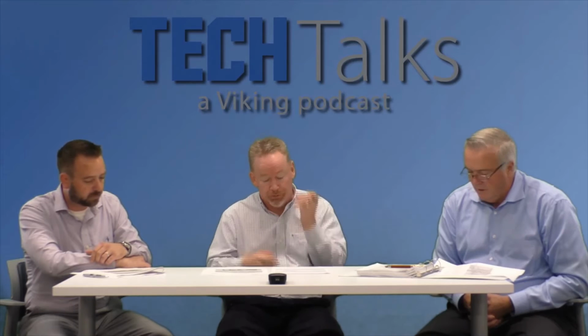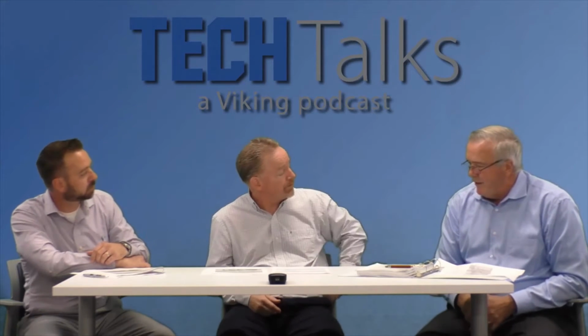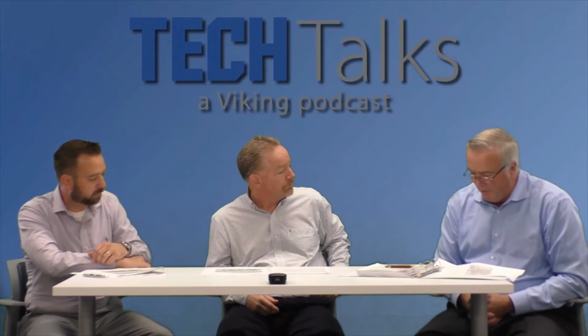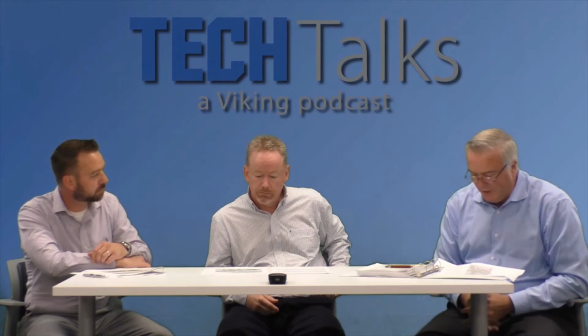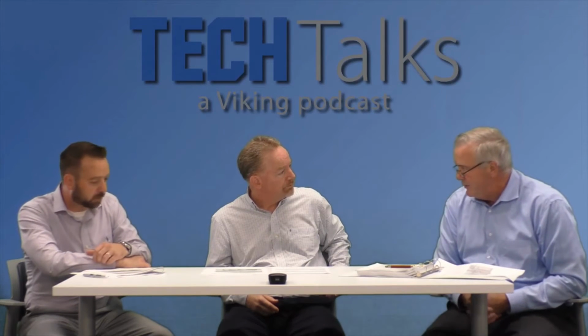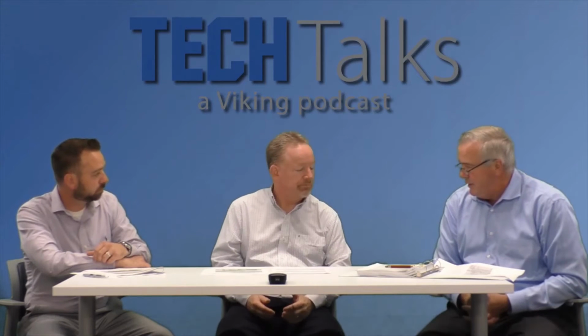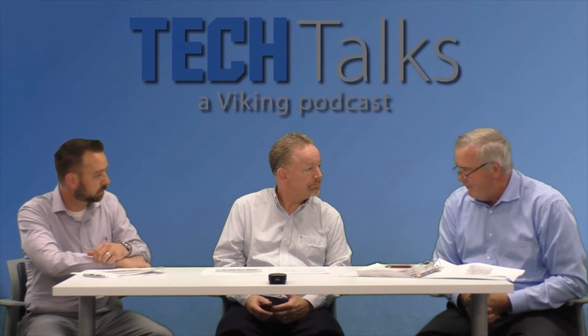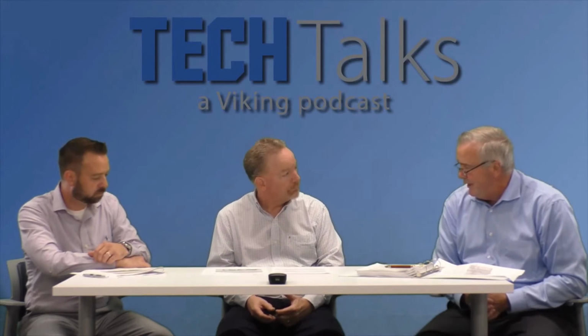Let's move over. I mean, both of you have mentioned. One other thing in the change in the tables is that the upright ESFR lost a little bit of its protection criteria because it dropped, for an example, in Table 8, it dropped to 25-foot ceilings, where it used to be at 30-foot ceilings. Oh, that's a hidden one, yeah. In some applications, I believe it even went to 35-foot ceilings. But it has dropped down to 25-foot ceilings for many applications.